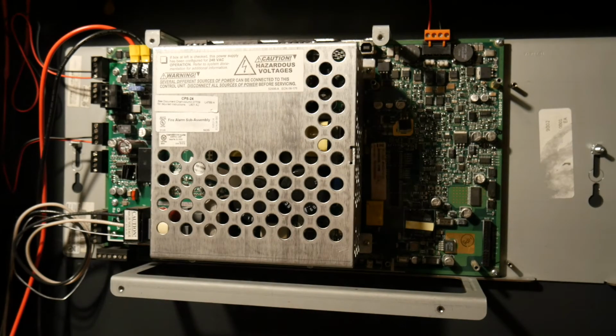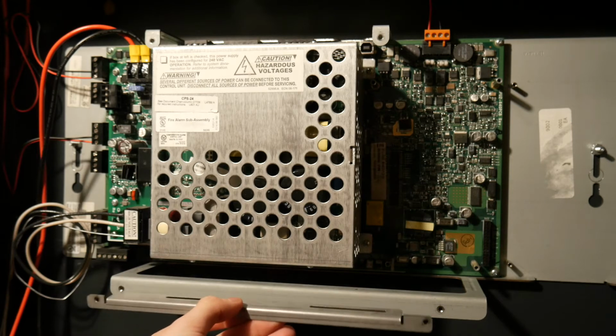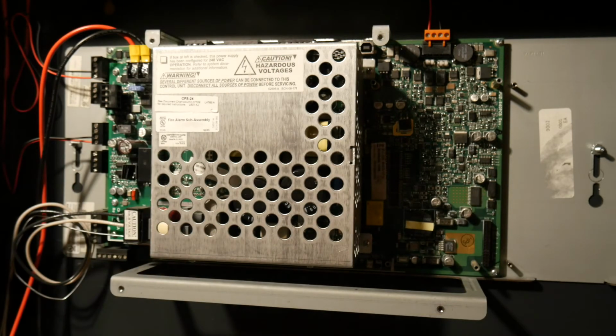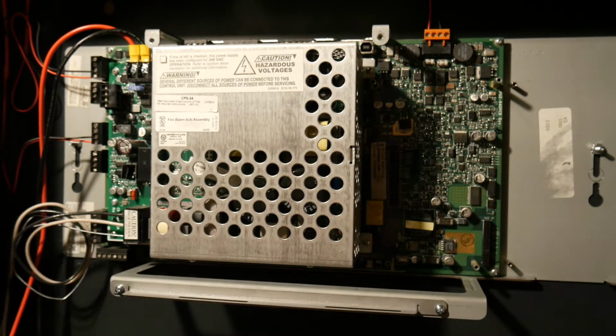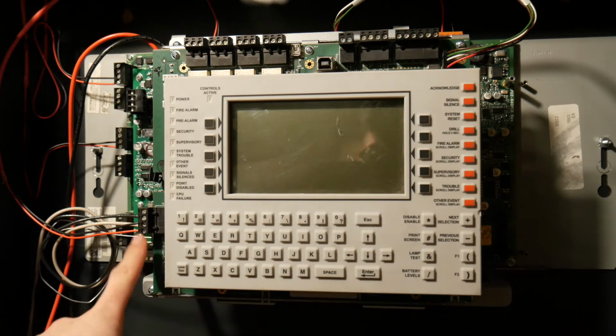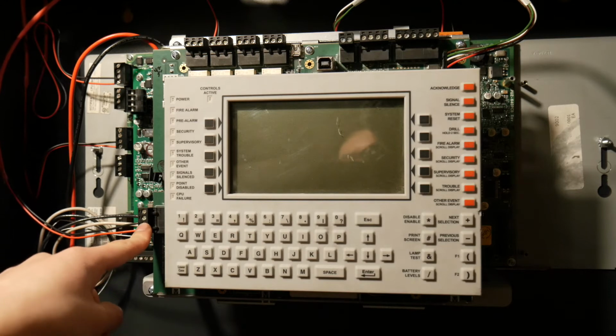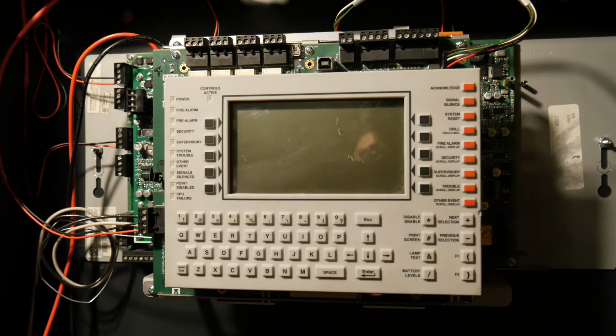So basically, you attach these two pieces right here, and the other one on top of there, and then you mount the NCA2. I'll be doing that right now. First, let me get a screwdriver, and then I'll mount this. Okay, so I mounted the NCA2. As you can see, I have my DC power coming from our non-resettable 24 volts from the main CPU, and my NUP cable right here going to the main CPU.